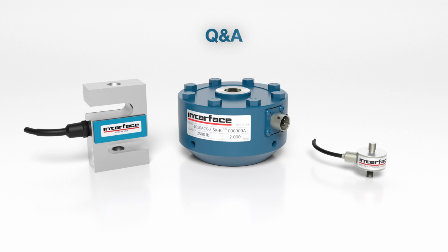Okay, are there shunt cal values available on every cal sheet as a normal routine, or do they need to be requested at the time of order placement? For standard product, shunt cal values will be noted on all calibration certificates. From an instrumentation level, if you're ordering a system setup and we are calibrating the load cell and the instrumentation at the same time, then a shunt cal value would also be noted on that.